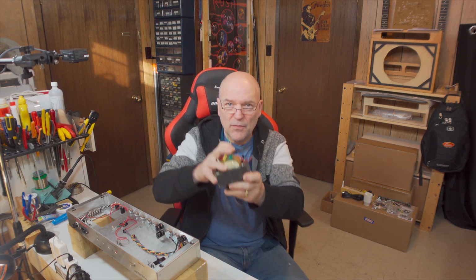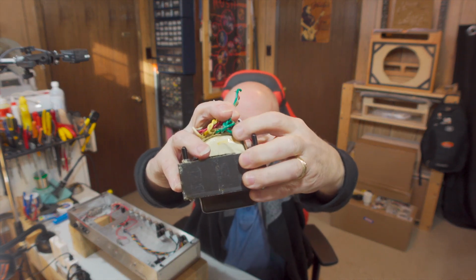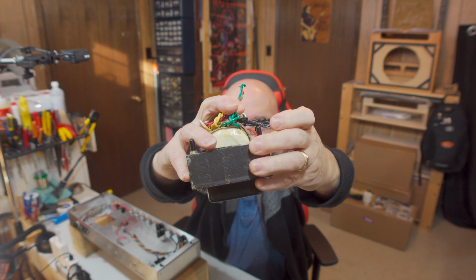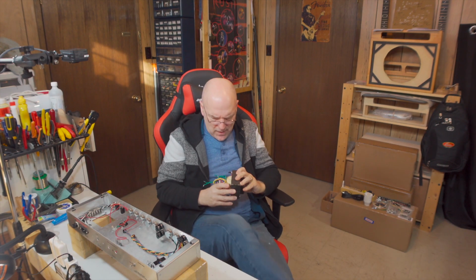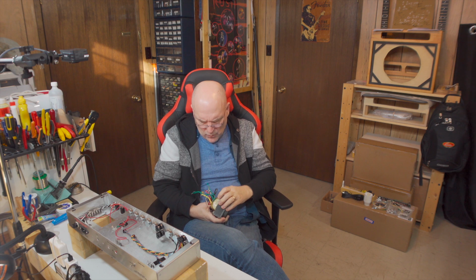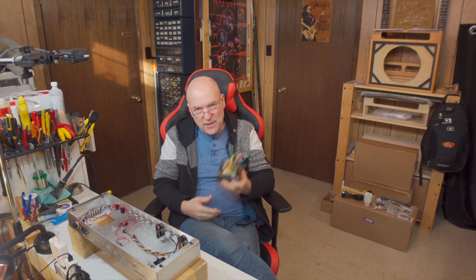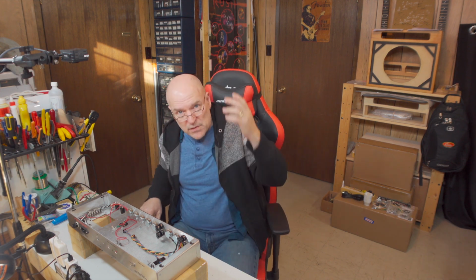some sticky sort of burning plastic. And I took a look, and sure enough, I don't know if you can see this, there is a burn spot right there. So that insulation was melting from the heat. So right off the bat, to me, that says that the transformer is arcing internally. It doesn't necessarily mean that's where the problem is. So the first thing I did was remove the transformer, disconnect all of the wires, and take the transformer right out. And then before doing anything else, you can check whether it's something that you did.